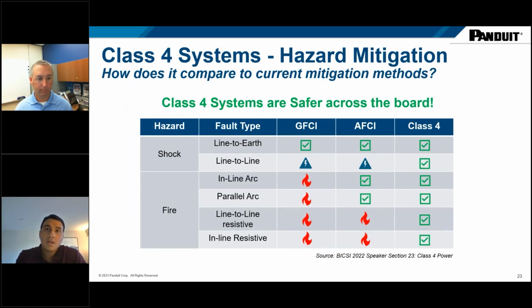So if we compare all these faults that we have to look at to existing hazard mitigation methods that we know of: we're all very familiar with GFCI outlets that are in our homes, in our bathrooms and kitchens. Those really are only good for one type of fault. AFCI adds a little bit more protection. It adds in-line arc and parallel arc. So these are also specific types of outlets. But now you have class 4, which detects all 7 different types of faults. And so one could say that class 4 power distribution is really safer than what we have running in our homes today.